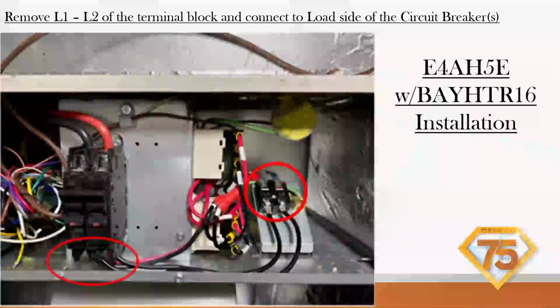In the beginning it wasn't stated, so we were adding some wire from L1, L2, but now in the installation manual, it will state remove these spade connectors. You can actually remove this terminal block, and you're going to land that on the load side. This is the line side. This is coming from the panel. The load side is going to all the unit.